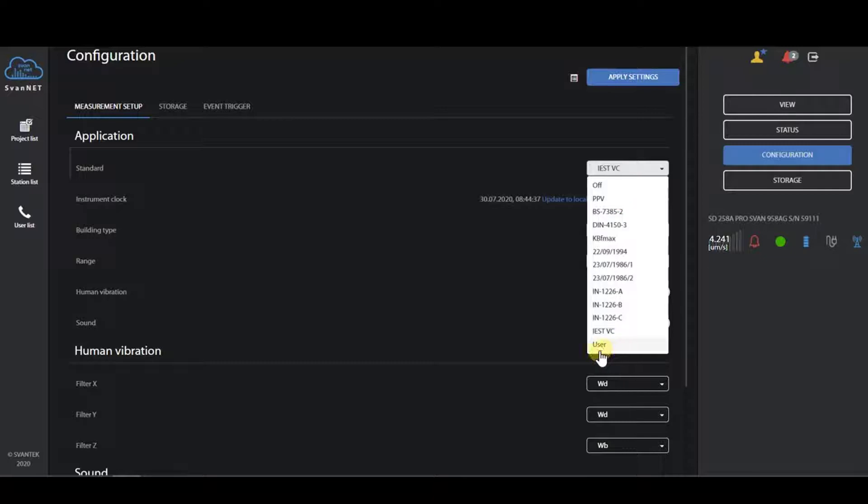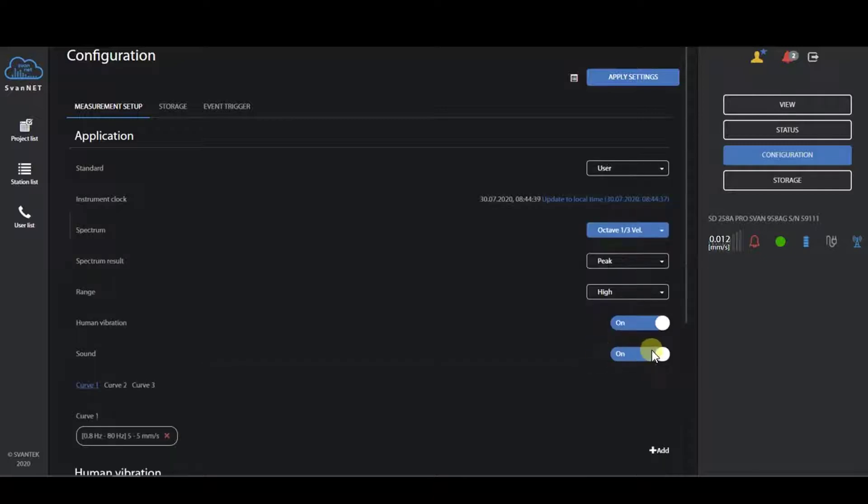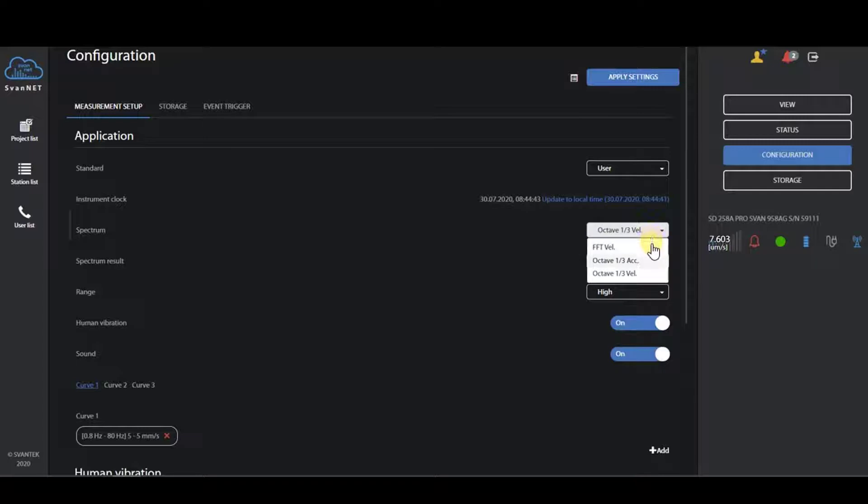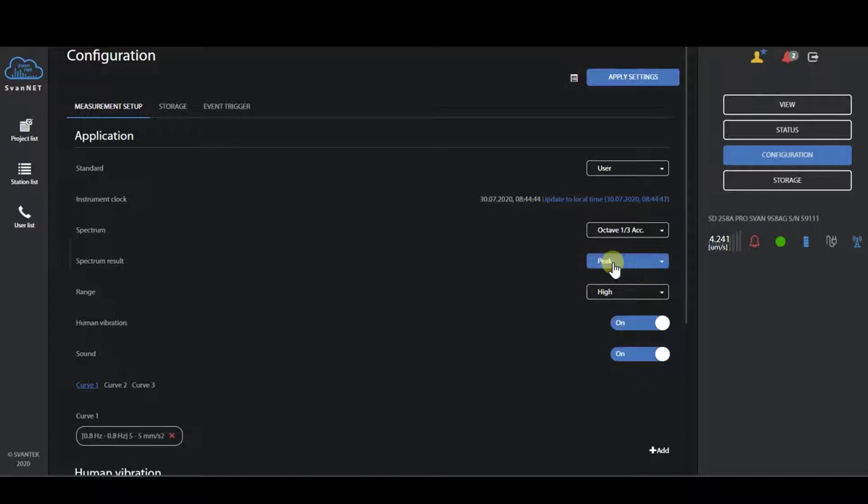We have also worked on user-defined curves, one-third octave user curves in acceleration or velocity with selection for peak, max, min, and RMS spectrum.